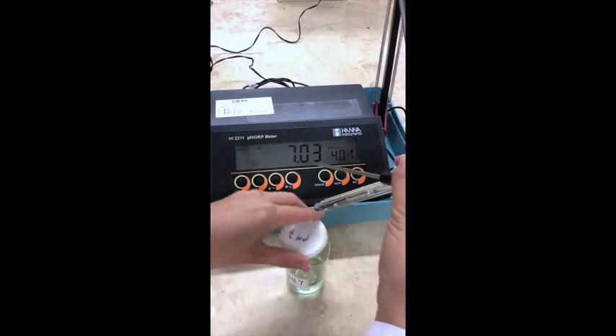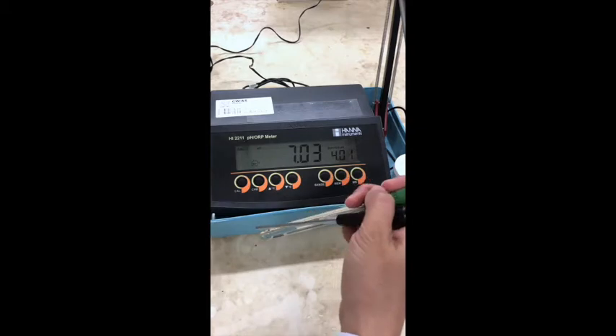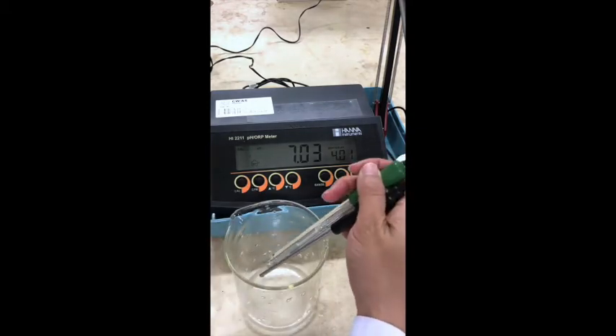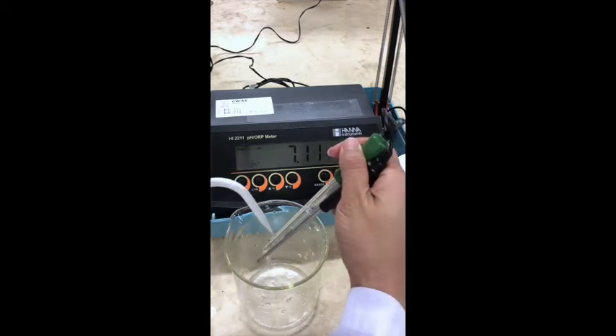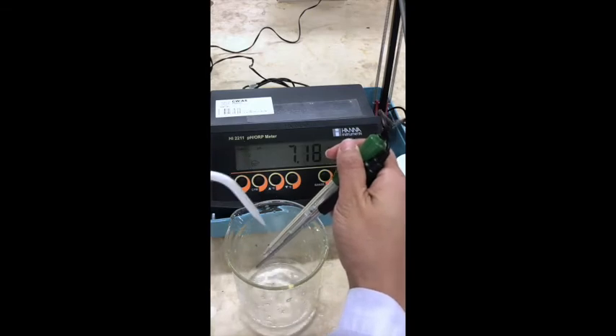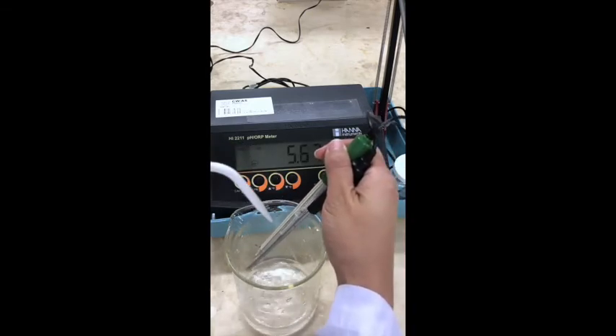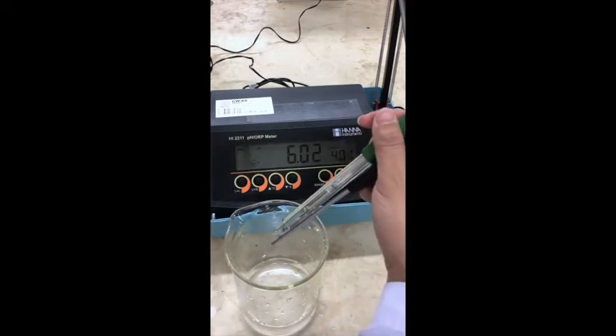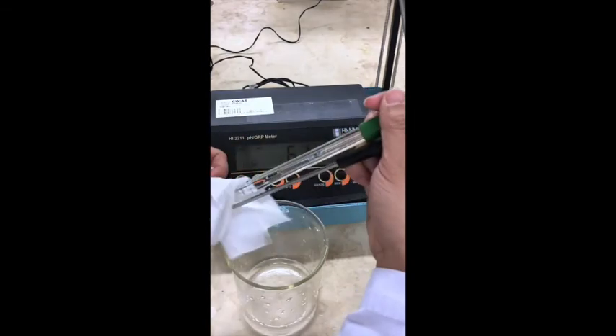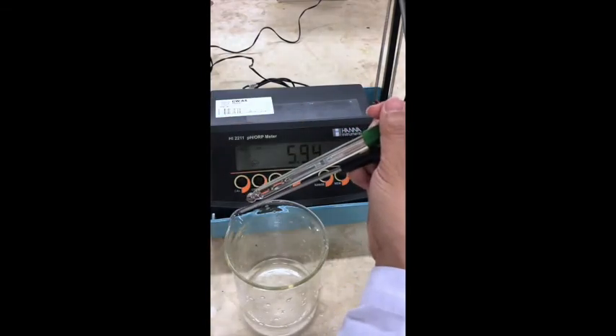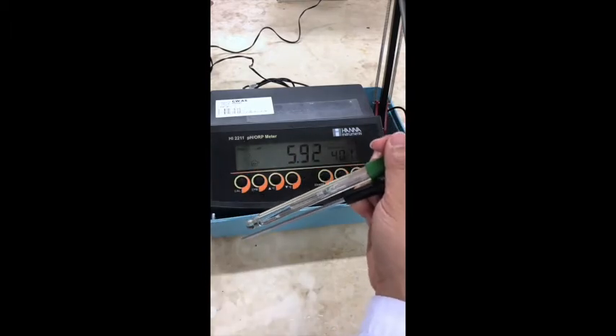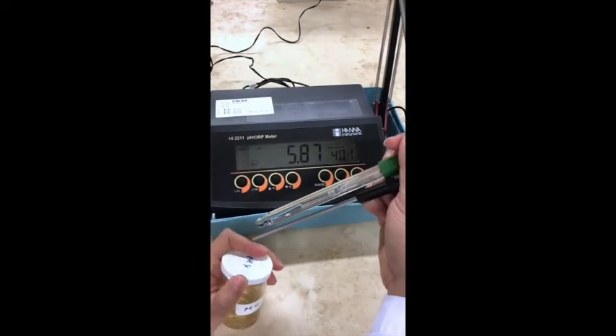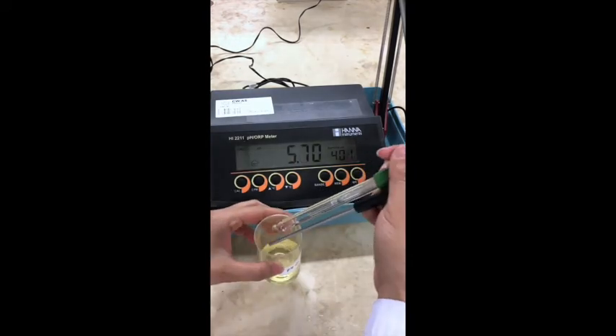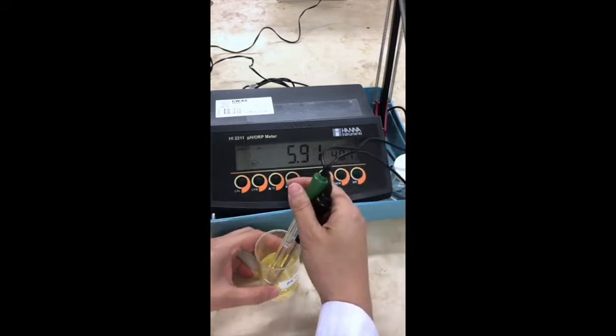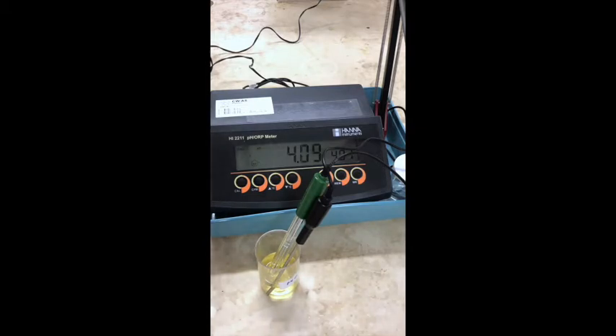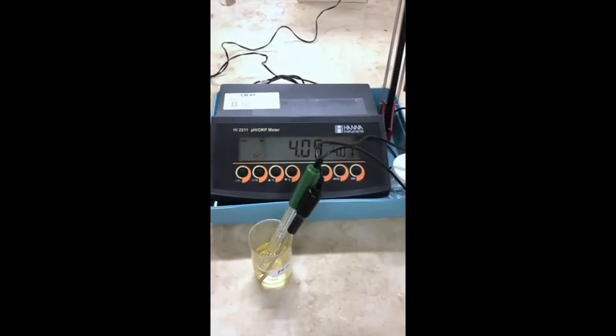Place the probe and the thermocouple into the buffer with pH 4. Before that, rinse the probe and the thermocouple with deionized water, and then clean the surface water with the lens paper again. Place the probe and the thermocouple into the buffer solution with pH 4. Stir the bottle to mix the content well. Wait until the potential measurement becomes steady.